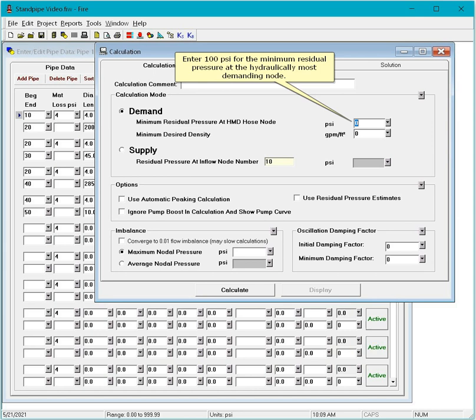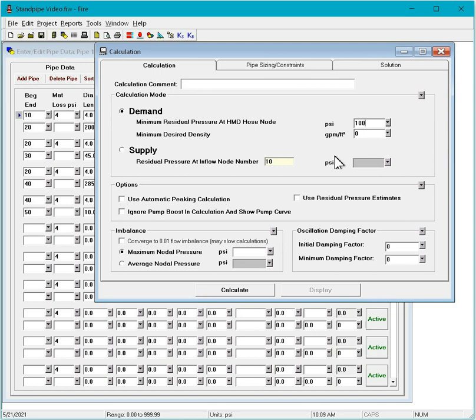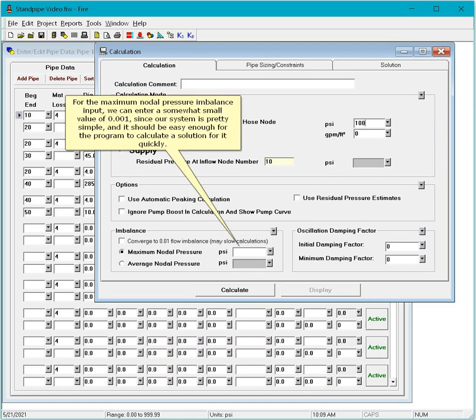Enter 100 PSI for the minimum residual pressure at the hydraulically most demanding node. For the maximum nodal pressure imbalance input, we can enter a somewhat small value of 0.001 since our system is pretty simple, and it should be easy enough for the program to calculate a solution for it quickly.